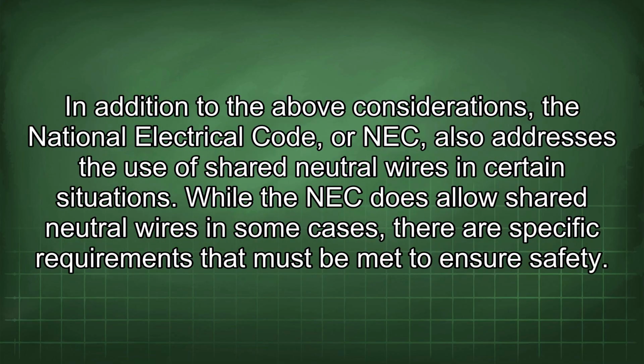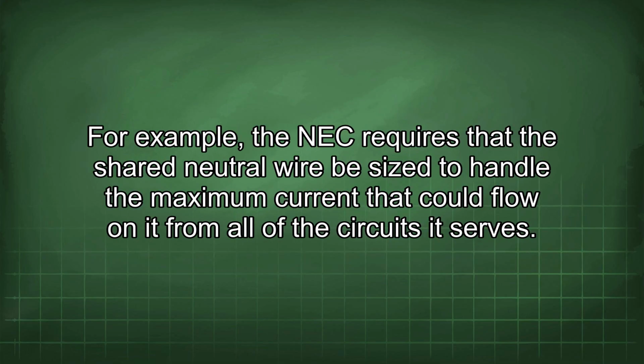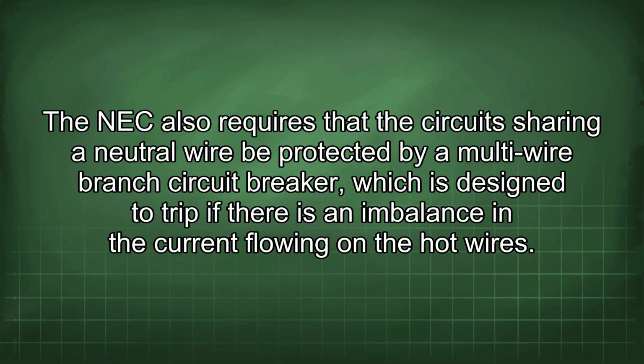In addition to the above considerations, the National Electrical Code, or NEC, also addresses the use of shared neutral wires in certain situations. While the NEC does allow shared neutral wires, in some cases there are specific requirements that must be met to ensure safety. For example, the NEC requires that the shared neutral wire be sized to handle the maximum current that could flow on it from all of the circuits it serves. The NEC also requires that the circuits sharing a neutral wire be protected by a multi-wire branch circuit breaker, which is designed to trip if there is an imbalance in the current flowing on the hot wires.